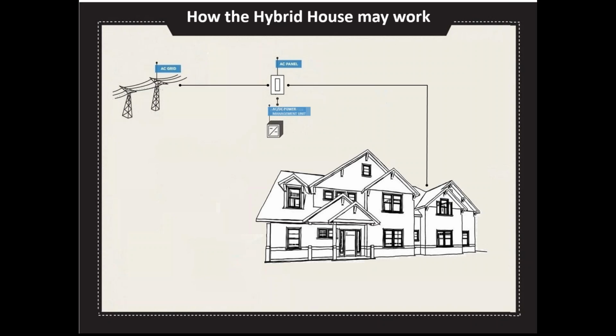The hybrid house would operate a little differently. Coming off the power panel, power would be redirected to an AC/DC power management unit, which could be a highly effective inverter. From the management unit, it would go to a DC power distribution panel. This would not be the same as a regular AC distribution panel, as DC power requires its own type of circuit breakers, so there's a distinction there, and compatibility to address.